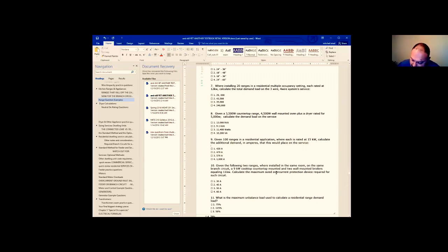So what if it was 5? I will do the 85%. Oh, if you had 5 of them? Yeah, like for example, on the table it says 5, 85%. If you had 5 of them, and each one of them at least 5,000 watts, it would be 25,000 times 85%, and that would be the way to derate.